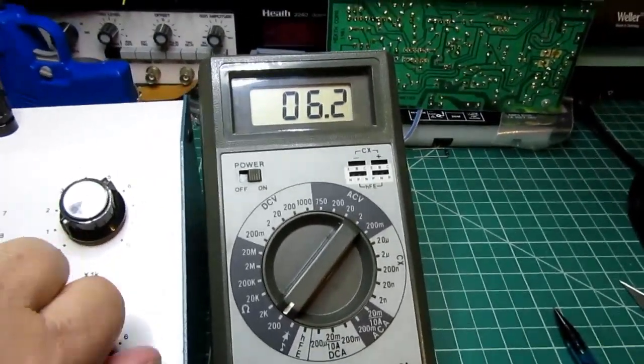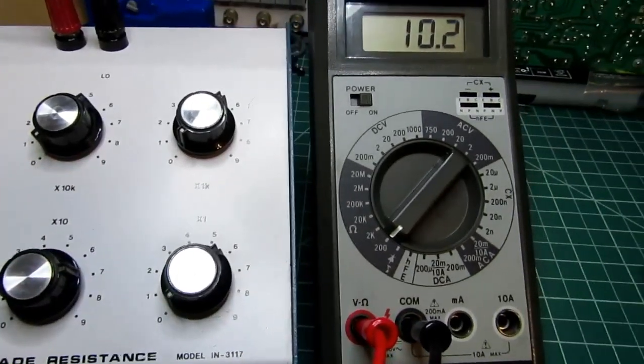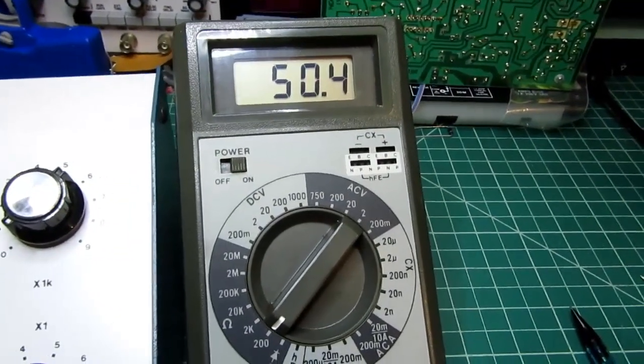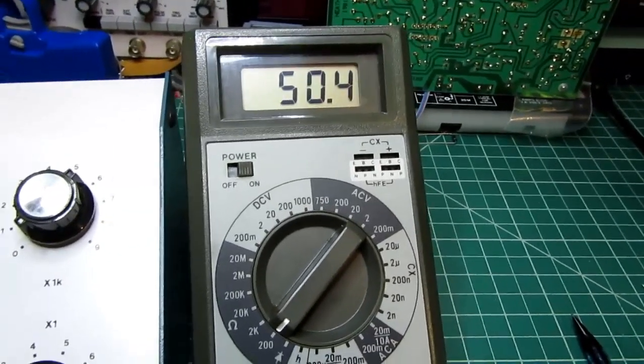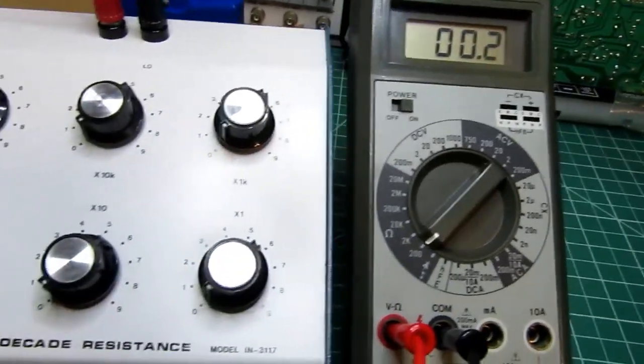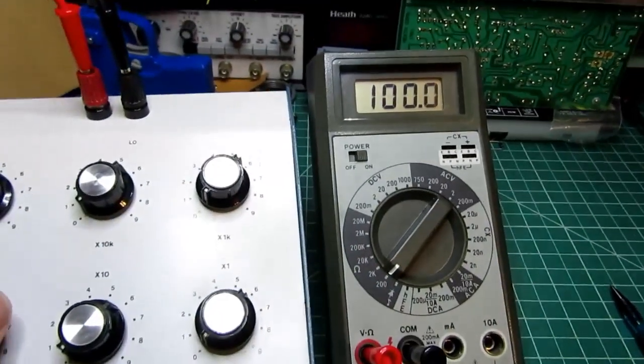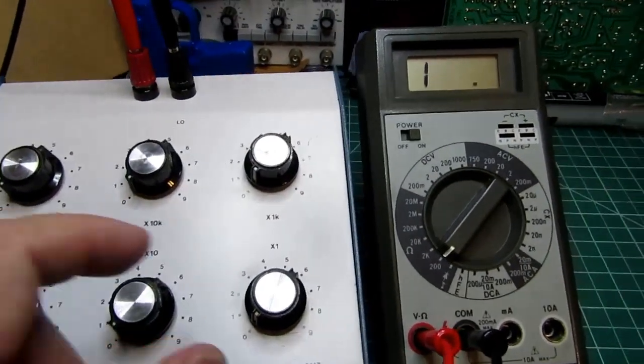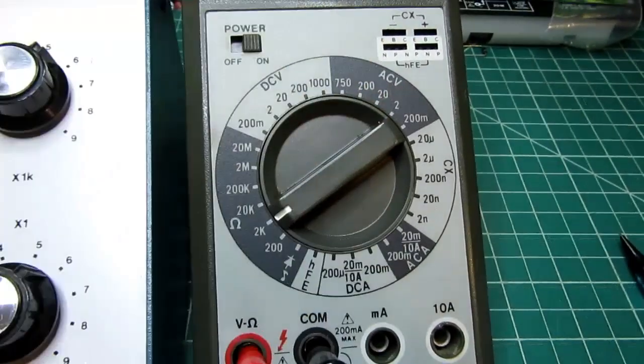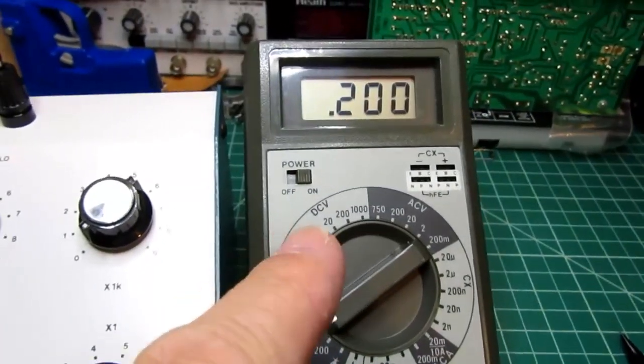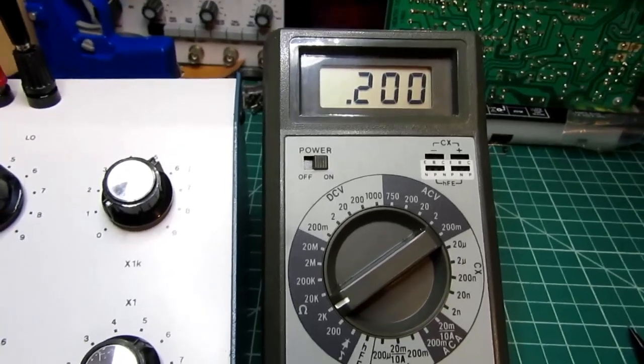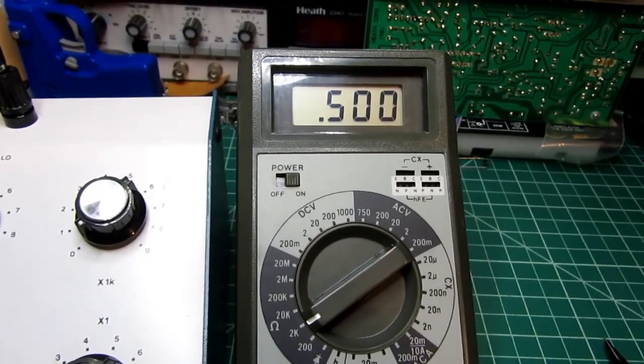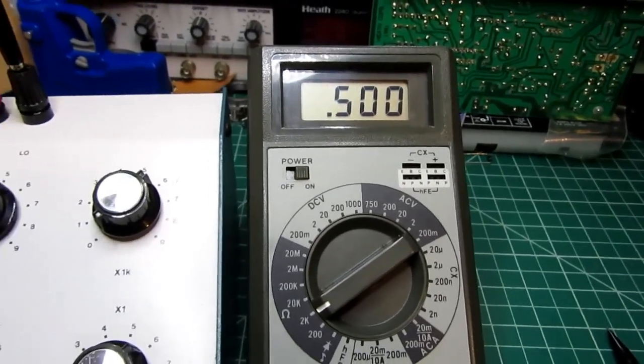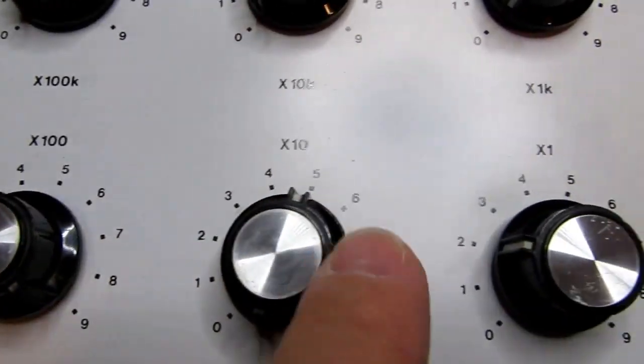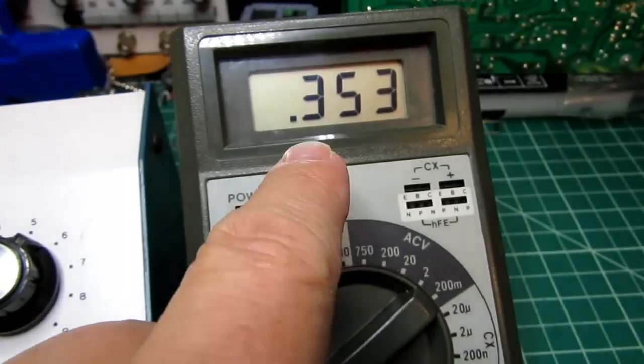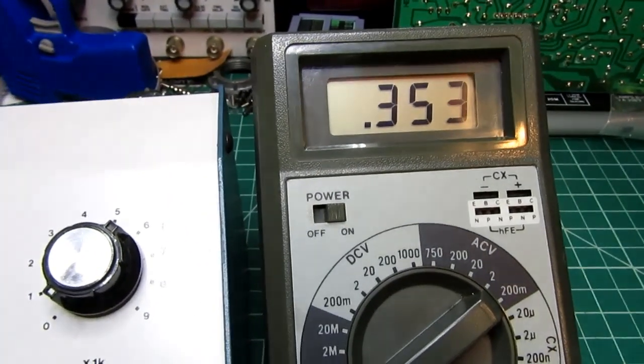Okay, that gets me up to 9 ohms, and I'm going on to the 10 range. 10, let's just go up to 50, 80. It's reading pretty well. It's well within tolerance. Now I can go to 100, and that's 200, but I'm overranged. So I switch to the 2K range, and I've got 0.2 K, or 200 ohms. 3, 4, 5, 6, 7, etc. Let's go to 352 ohms, and we're reading 353 ohms, or 0.353 K.